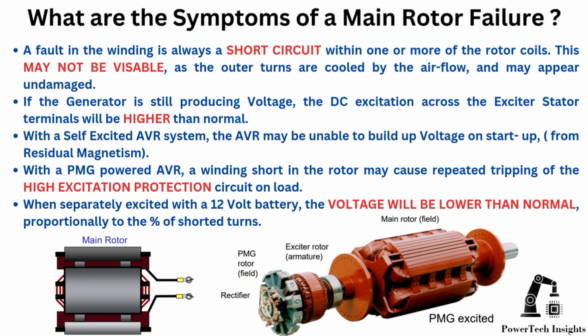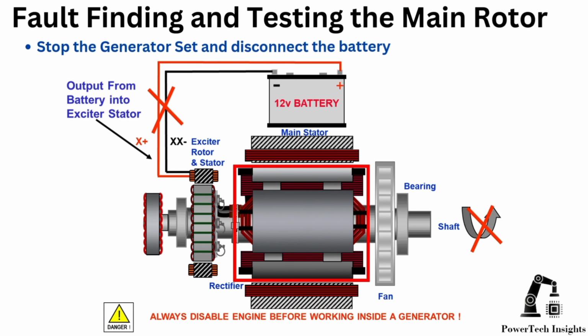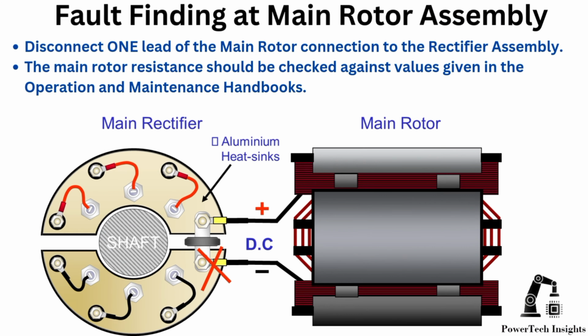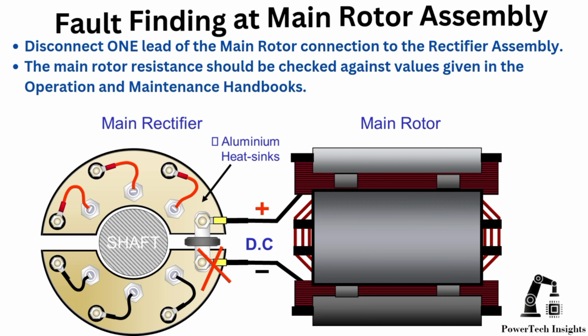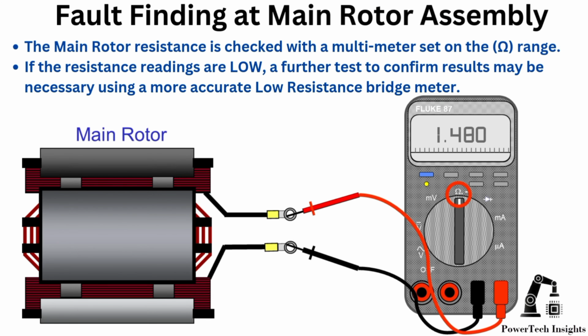Fault finding and testing the main rotor winding. Stop the generator set and disconnect the battery. Follow lockout-tagout procedure. Disconnect one lead of the main rotor connection to the rectifier assembly. The main rotor resistance should be checked against values given in the operation and maintenance handbooks. The main rotor resistance is checked with a multimeter set on the ohm range. If the resistance readings are low, a further test to confirm results may be necessary using a more accurate low resistance bridge meter.